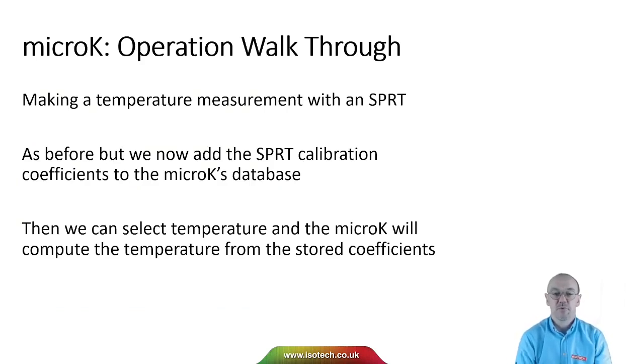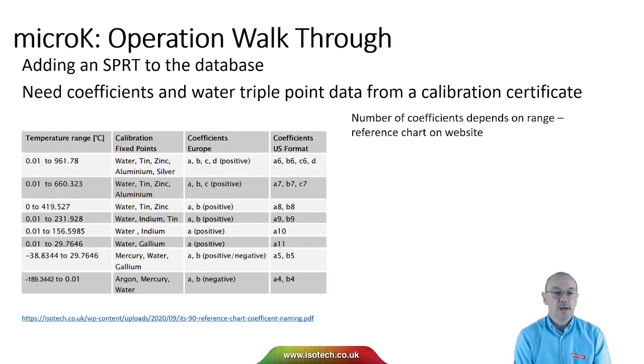It's pretty much the same as before, but now we need to add the SPRT calibration coefficients to the MicroK's database, and then we can select temperature, and the MicroK will compute the temperature from the stored coefficients. So from the calibration certificate for the SPRT, we need to take the coefficient, and we need a recent value for the resistance of the SPRT at the water triple point. So the number of coefficients we need will vary with the temperature range. This chart here shows the different coefficients for the different ITS-90 sub-ranges.